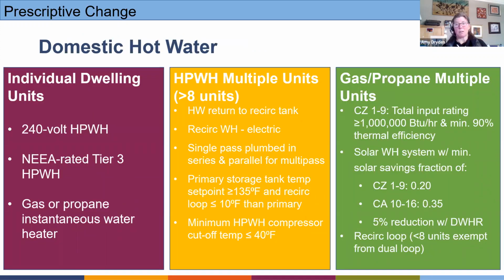For domestic hot water, which is one of the biggest loads and key end uses, I would say, in multifamily, there are 3 different options that can be installed. So we talked about the individual dwelling units, where we can do a 240 volt heat pump water heater. It's going to be NEEA rated tier 3. And you can even do a gas or propane instantaneous water heater.